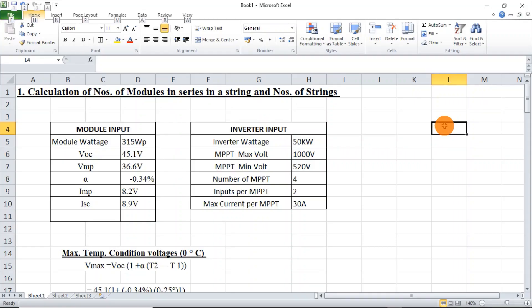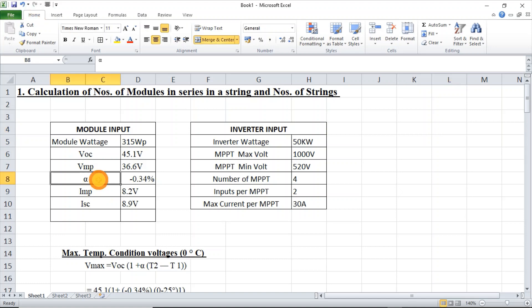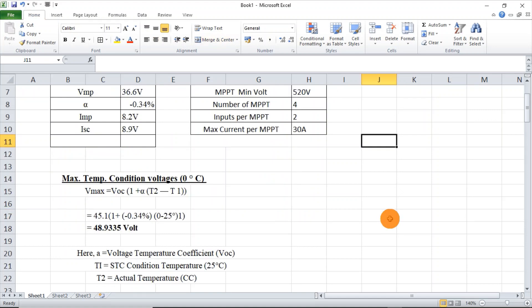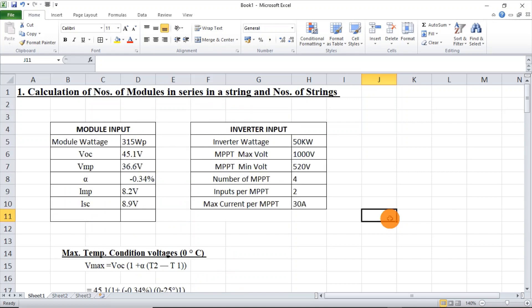Hi guys, let's see how to calculate the number of modules in series in a string and the total number of strings to be connected in an inverter. For this we need some inputs from the module as well as from the inverter. Taking a module of 315 watt peak, we take its VOC, VMP, ISC, and IMP. Alpha represents the temperature coefficient, which you can get from the datasheet. This is the change in temperature that will affect the voltage of the module, so we have to take this into consideration.